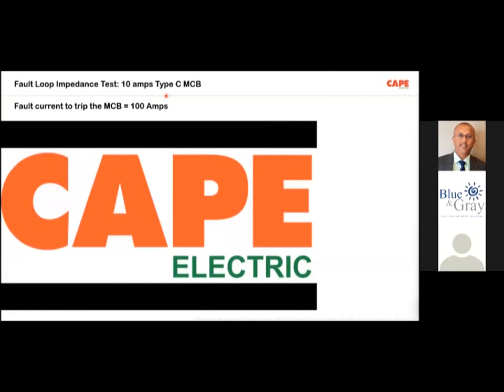So our aim is to ensure that the MCB is tripping within 0.2 seconds. Of course, even if your equipment burns for about 3 seconds, nothing happens. A fault or heat dissipated from an electrical equipment, whatever the amount of power it is, if it is disconnected within 3 seconds, then the chance of fire is almost negligible. And this test is actually to ensure that your devices are operating properly.